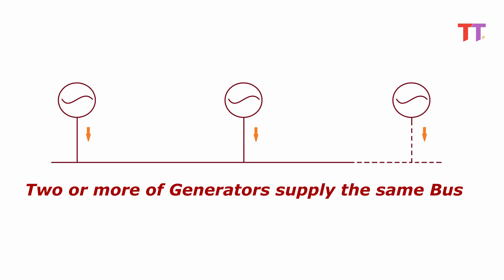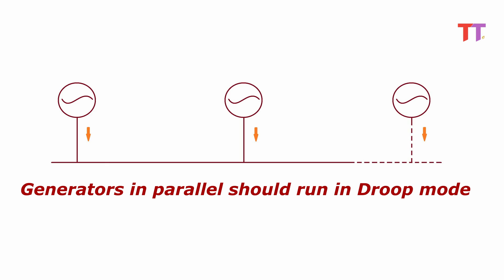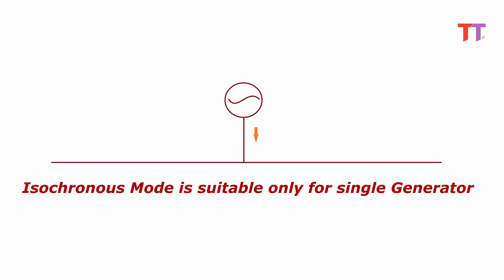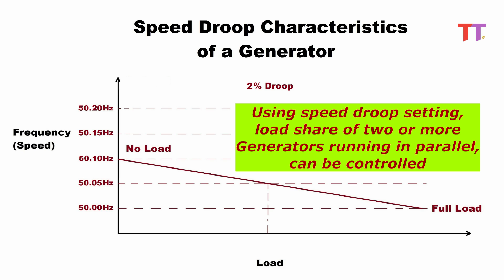Generally two or more generators supply the same bus. These generators in parallel should run in droop mode. In isochronous mode there is no scope for control of load share of generators, hence isochronous mode is suitable only for a single generator. Whereas using speed droop setting, load share of two or more generators running in parallel can be controlled.